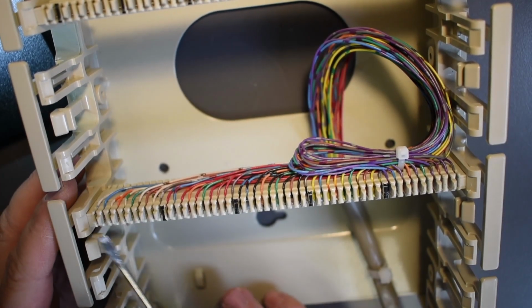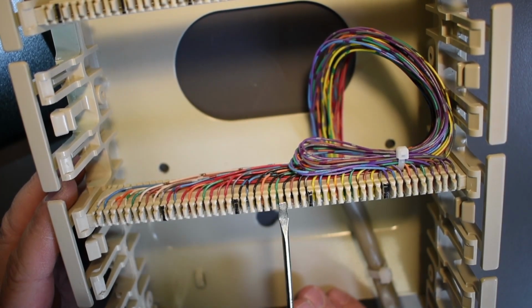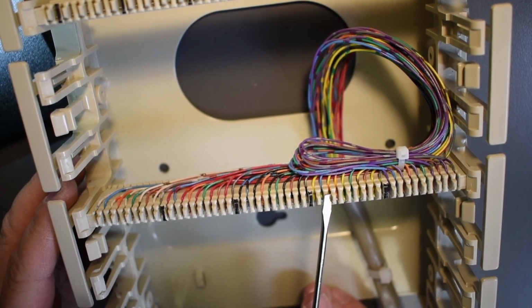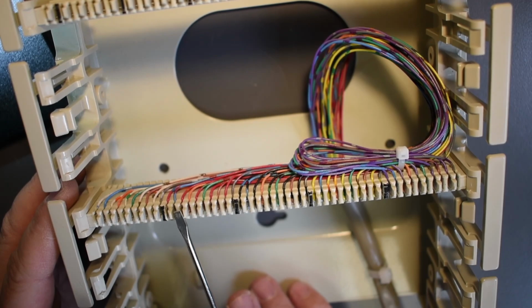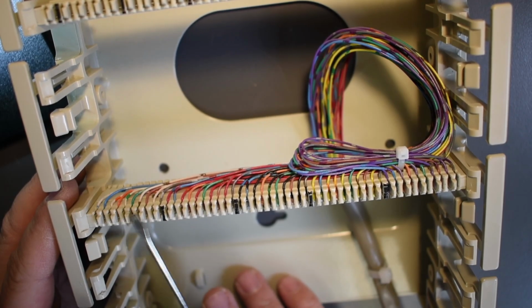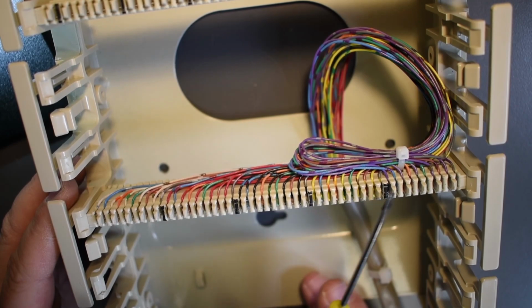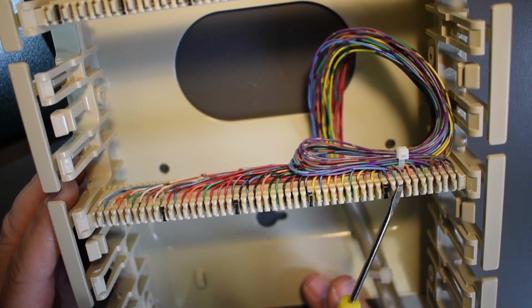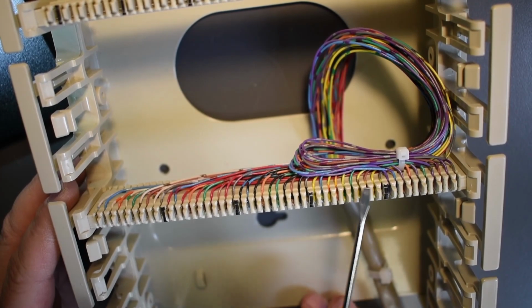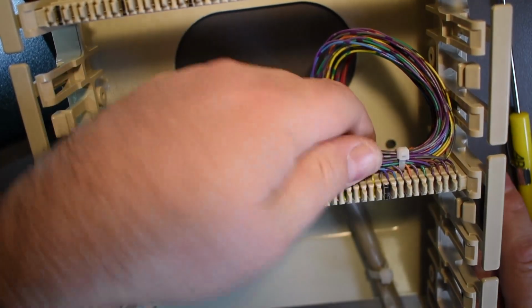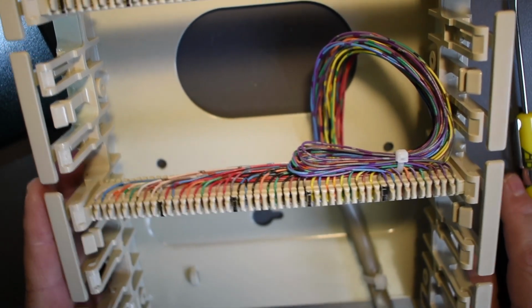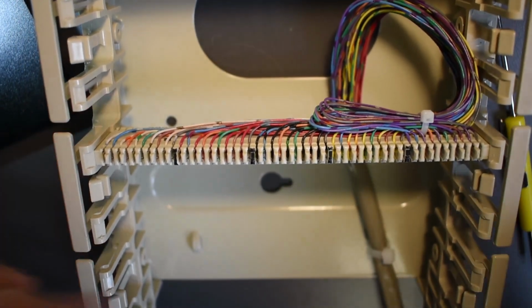I want to see it nice and clear so I can tell the colors when I'm marking your work. I want to make sure that none of those have moved or jumped from one place to the other by accident. Before you give your job to the client, you hand it over, you should make sure that you just go once over to see that you haven't done anything you shouldn't have by mistake. And sometimes it happens, a pair just gets flipped. Okay? And that is not good if you are giving a working system that has to be reliable to a client. Okay? So that's the first picture. Yeah, just frame it like that.